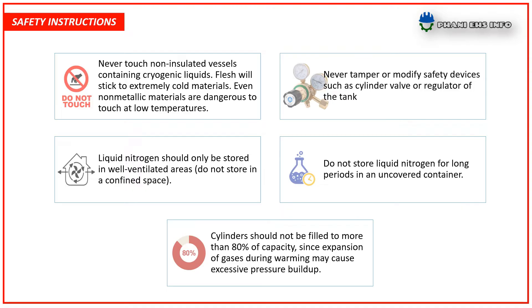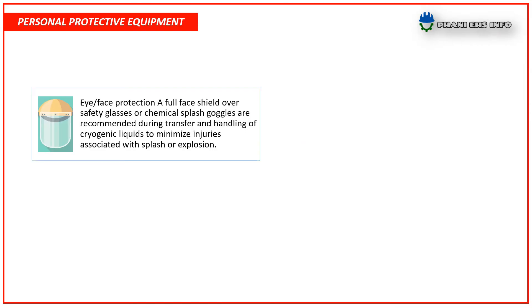Cylinders should not be filled to more than 80 percent of capacity, since expansion of the gases during warming may cause excessive pressure buildup.